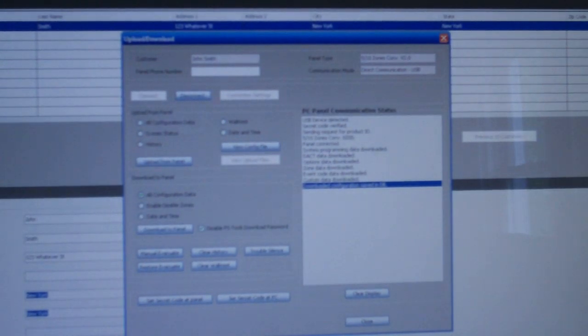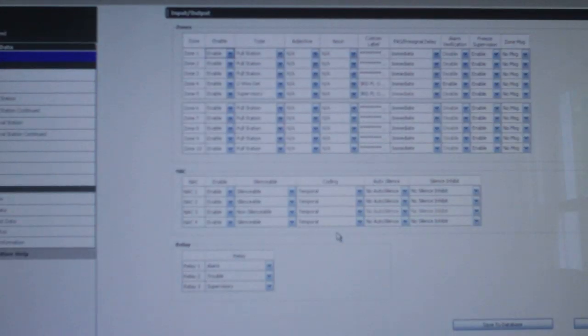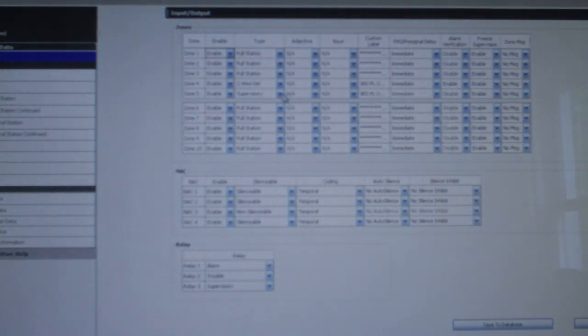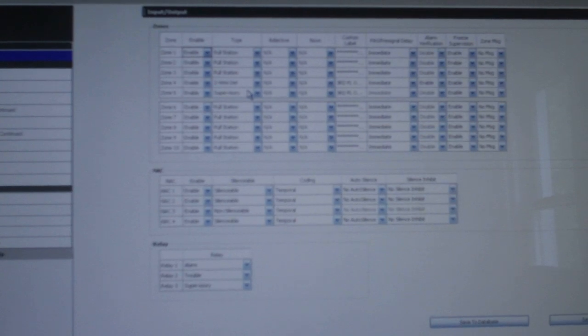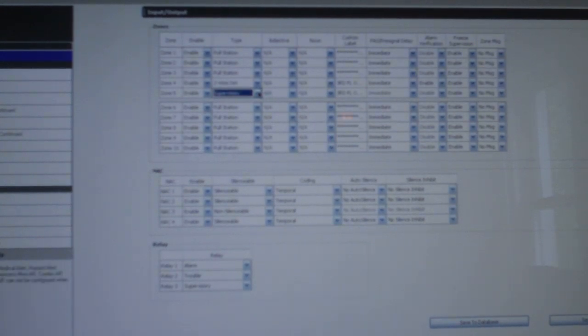Or maybe not. Apparently, somehow zone 5 has turned into a supervisory. I don't know how that happened, but oh boy. Let me go back into configure. And yeah, for some reason zone 5 is supervisory. I don't know how that happened. Let's make it pull station.